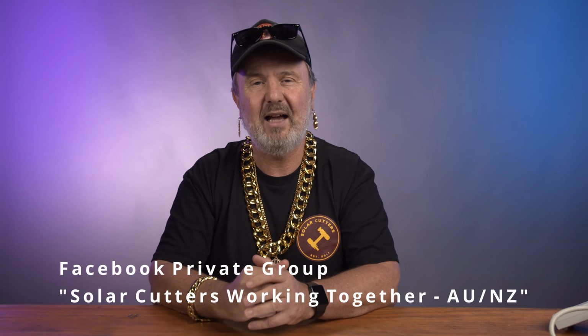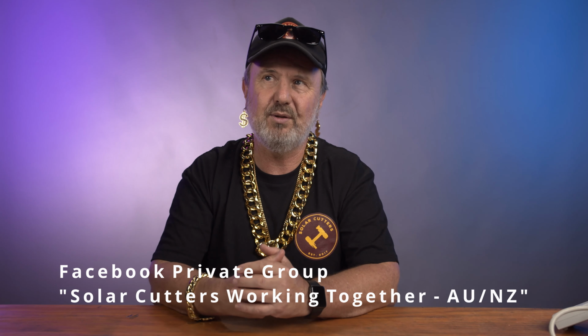Now, before I started recording this, I actually had a question come in on the Solar Cutters page. It was a result of a comment I made to one of the installers there about a generator supplying an interactive inverter. I made the comment that I hope this inverter is connected by fixed wiring as per clause 9.4.2 from AS/NZS 4509.1, the 2009 edition, which is actually the latest version. And the comments came back, can you please explain what's meant by that?